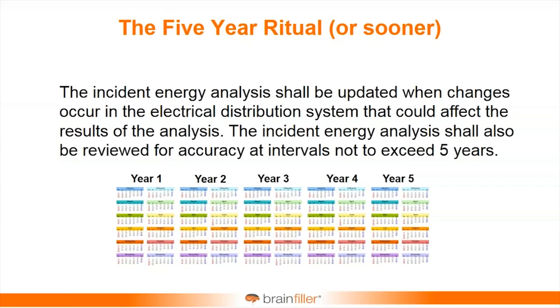In NFPA 70E, as many of you know, you're required to go back and revisit the labels, the analysis, the study at intervals not to exceed five years, or if there's any significant change that could affect the results. I look at 'affecting the results' as meaning could it affect the PPE that you wear, or maybe the arc flash boundary — where perhaps that may need to be increased. If it decreases, don't worry about it. But if it increases, that would affect your practices.